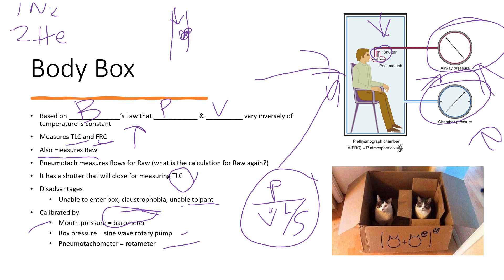To summarize: body plethysmography is based on Boyle's Law. Advantages include measuring TLC, FRC, and airway resistance with a shutter for total lung capacity. Disadvantages include inability to enter the box due to claustrophobia, body habitus, poor mobility, or inability to follow instructions. Calibration requires a barometer, sine wave rotary pump, and rotameter. If the patient can't use the body box, nitrogen washout or helium dilution are alternative methods for measuring total lung capacity.